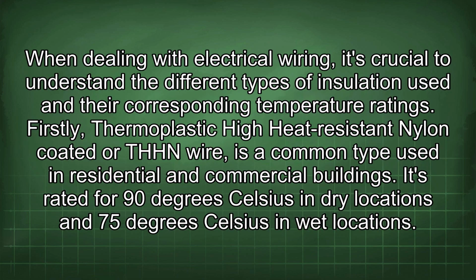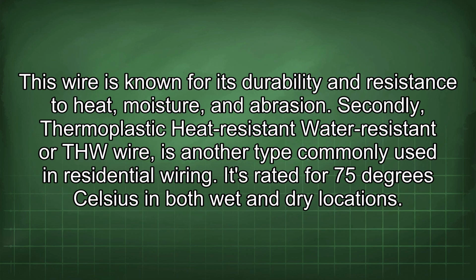When dealing with electrical wiring, it's crucial to understand the different types of insulation used and their corresponding temperature ratings. Firstly, thermoplastic high heat resistant nylon coated, or THHN, wire is a common type used in residential and commercial buildings. It's rated for 90 degrees Celsius in dry locations and 75 degrees Celsius in wet locations. This wire is known for its durability and resistance to heat, moisture, and abrasion.